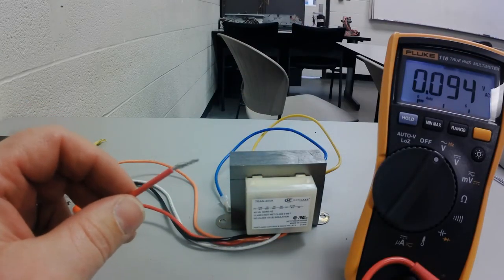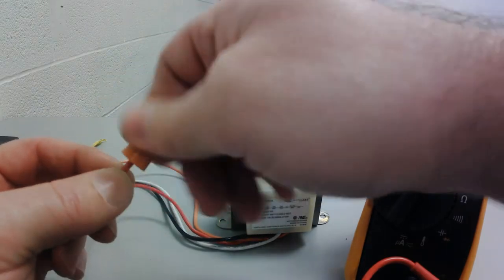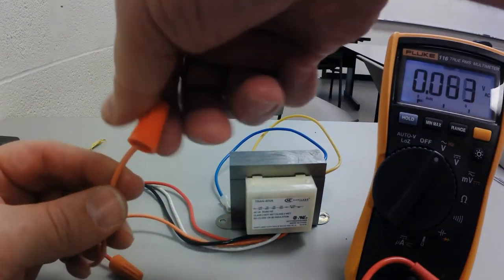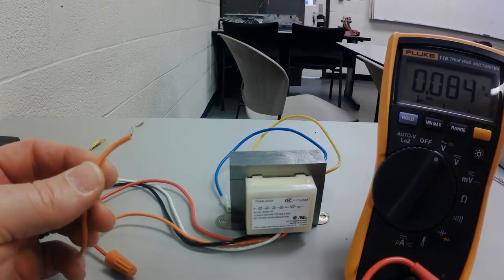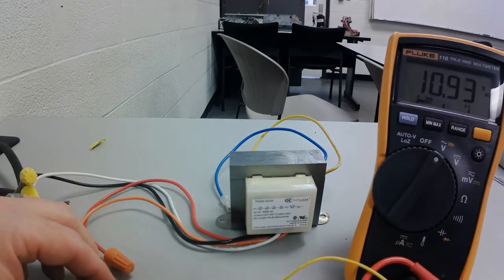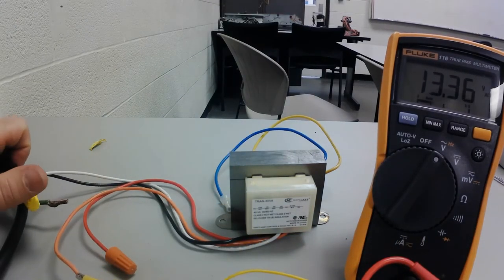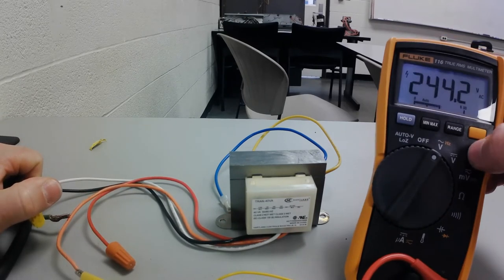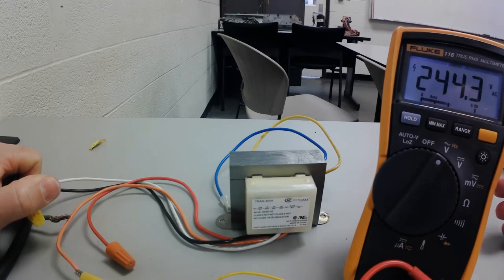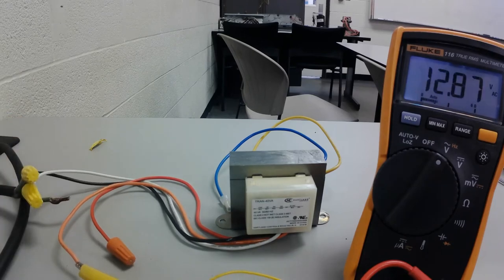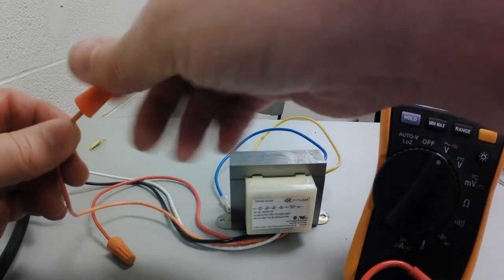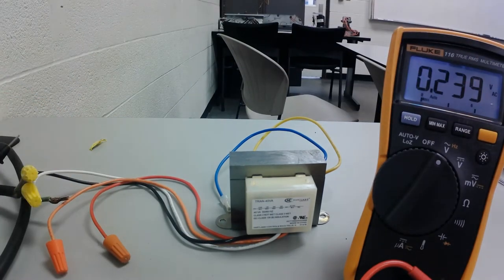So I'm gonna, and don't do this at home, I'm doing this for purposes of education, but I'm gonna take my orange. Now orange to black should be a 240 volt input, but I'm gonna use it here. All right, now look at that one, 244 volts. But all I did was, and I'm still putting in only 120 volt input on the primary side of this transformer. Okay, it's because all of these wiring taps, I'll call it, this multi-voltage tap, it comes off of one winding, really.